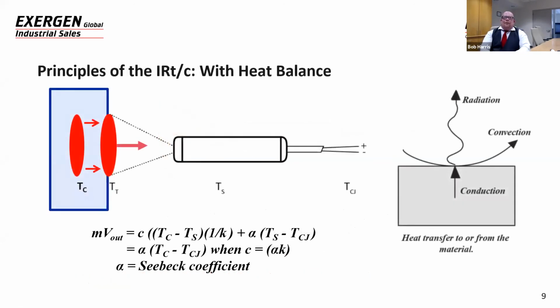So to take it to the next level, we can also calibrate the sensor, so then rather than just measuring the surface temperature, we can calibrate for the core temperature. In this example here, TC is the core temperature of that block. And as we know, the IRTC is going to measure the surface temperature, but we don't want the surface temperature. We want the core temperature.